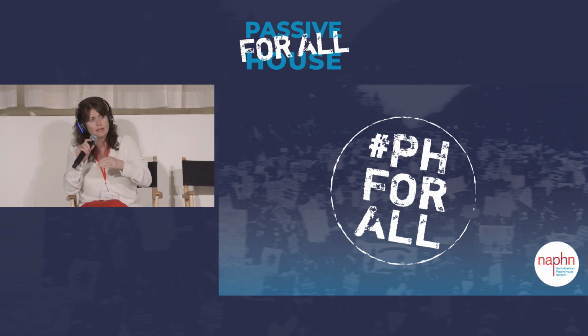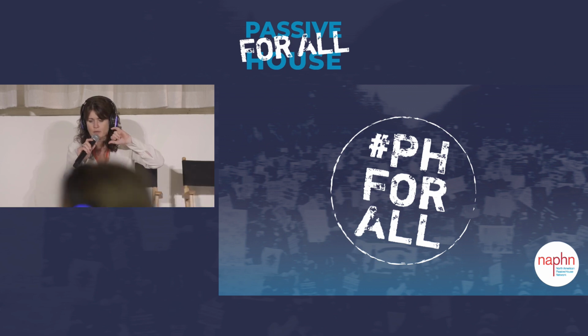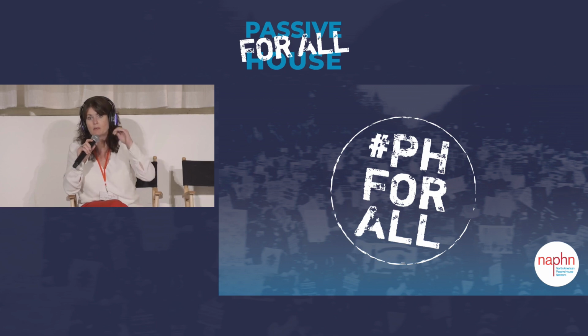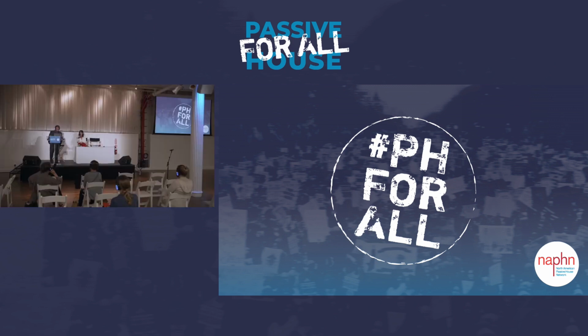The 10 foot has been changed, it's something, I don't know if it's 8 foot or the manufacturer's recommendation. It's either 6 or 8 feet now, because these aren't high pressure systems, and that 10 foot rule was meant for high pressure systems. So they're changing it, and if it hasn't come out yet, it's getting changed in this next version of the code. So that's been taken care of.